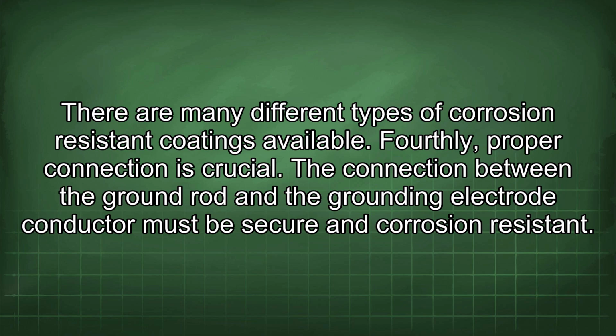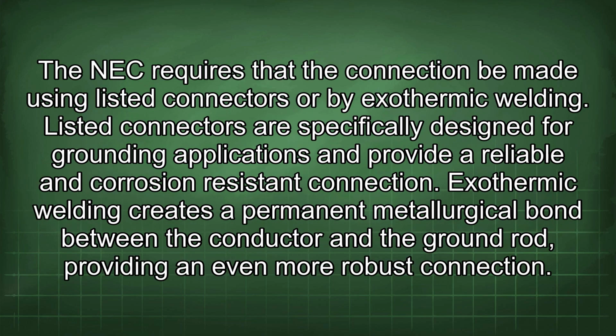Fourthly, proper connection is crucial. The connection between the ground rod and the grounding electrode conductor must be secure and corrosion-resistant. The NEC requires that the connection be made using listed connectors or by exothermic welding. Listed connectors are specifically designed for grounding applications and provide a reliable and corrosion-resistant connection. Exothermic welding creates a permanent metallurgical bond between the conductor and the ground rod, providing an even more robust connection.